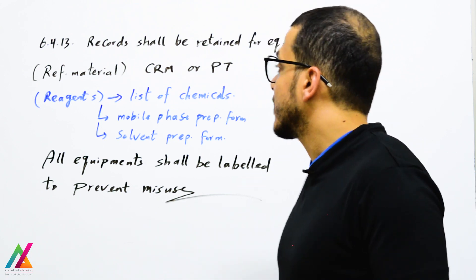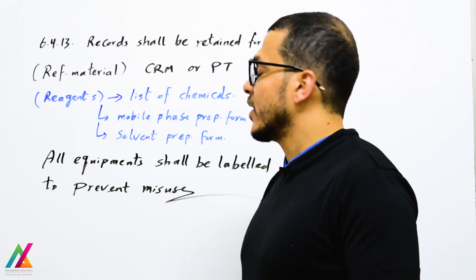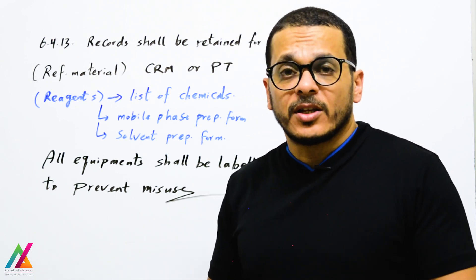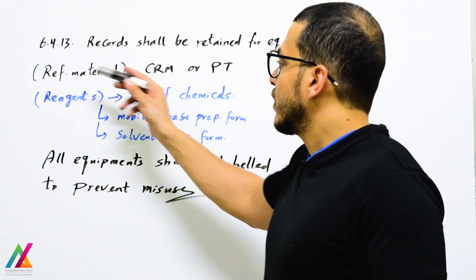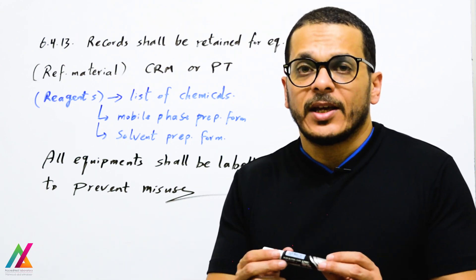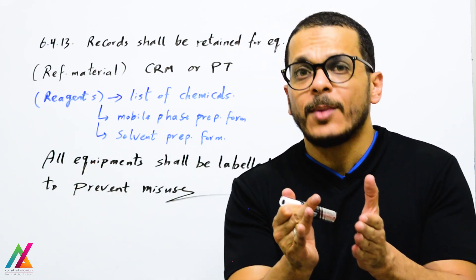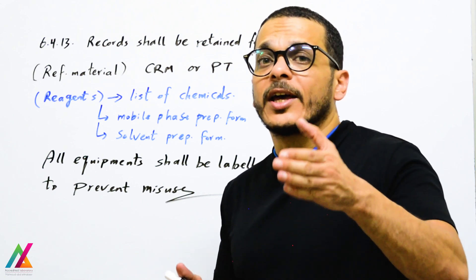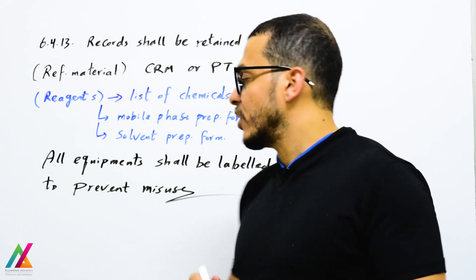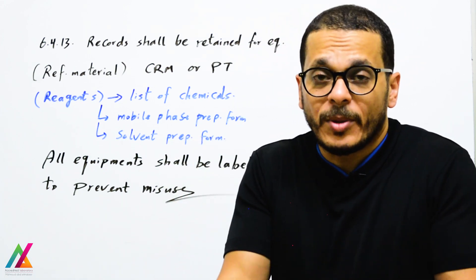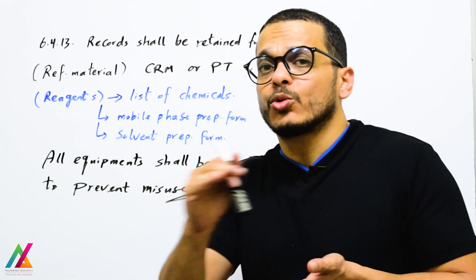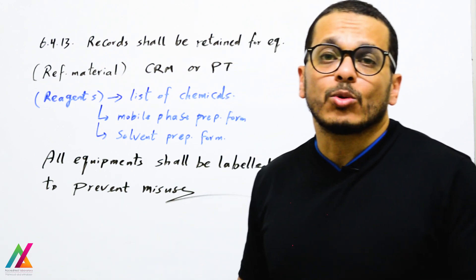Label all prepared standards clearly for everyone, including: name of the standard, preparation date, expiry date, preservation temperature, and initials. Reference materials such as CRM or PT samples are also considered equipment in the new edition — CRM providers shall meet ISO 17034 and PT providers shall meet ISO 17043. For reagents, maintain a list of all chemicals received including receiving date and expiry date. Prepare a mobile phase preparation form and a solvent preparation form for any solvents prepared in the lab.